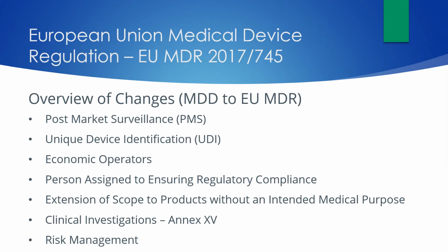Next, we will be discussing the overview of changes from Medical Device Directive to EU MDR. Specifically, there will be 7 key areas that we will touch upon. The first being post-market surveillance, or PMS. Notified bodies will be playing a bigger role in supervising the manufacturer's PMS system. For example, a PMS report or periodic safety update report will be required depending on device class.